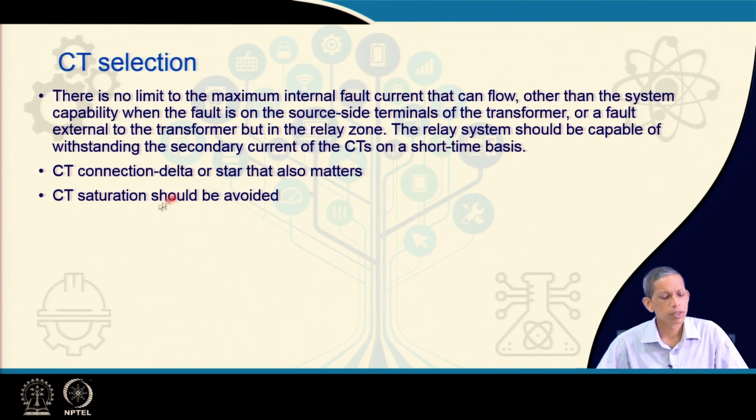The other attention is that CT saturation should be avoided. If there is CT saturation, then even for an external fault, differential current will flow during that time, and that may create problems for the relay decision process.